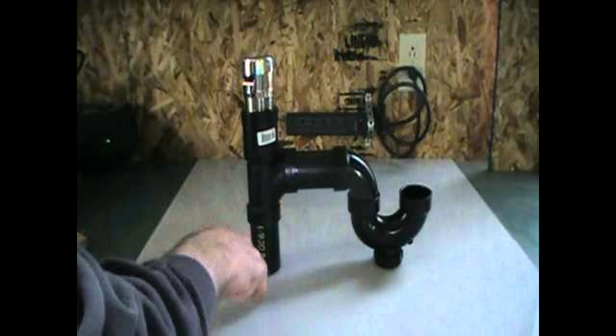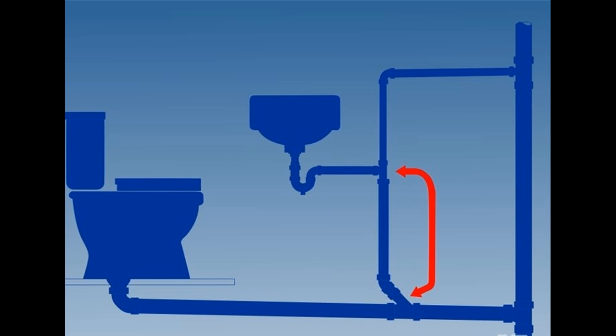Understand the general layout of piping. Vents and other vertical pipes should be as straight as possible to prevent condensation from building in the pipes. Horizontal pipes should slant down toward fixtures so that gravity can push waste and water through the pipes. These commonly run with a slope of 1/4 inch, 0.6 centimeters, down for each horizontal foot of piping.